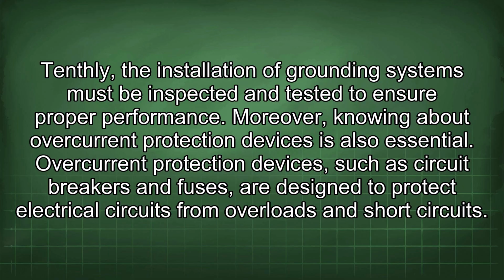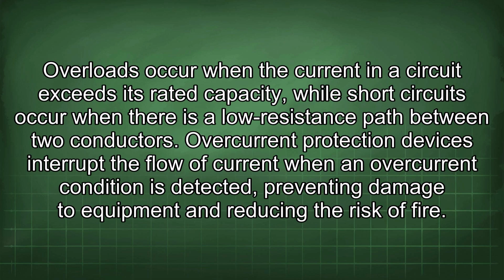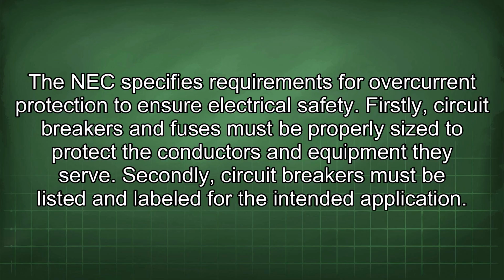Moreover, knowing about overcurrent protection devices is also essential. Overcurrent protection devices, such as circuit breakers and fuses, are designed to protect electrical circuits from overloads and short circuits. Overloads occur when the current in a circuit exceeds its rated capacity, while short circuits occur when there is a low resistance path between two conductors. Overcurrent protection devices interrupt the flow of current when an overcurrent condition is detected, preventing damage to equipment and reducing the risk of fire. The NEC specifies requirements for overcurrent protection to ensure electrical safety.